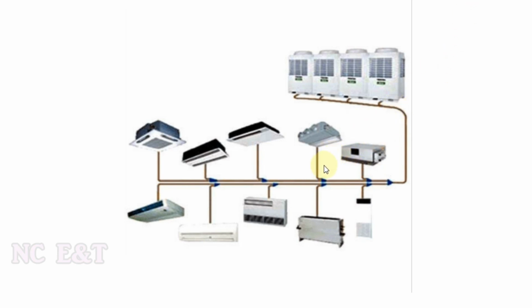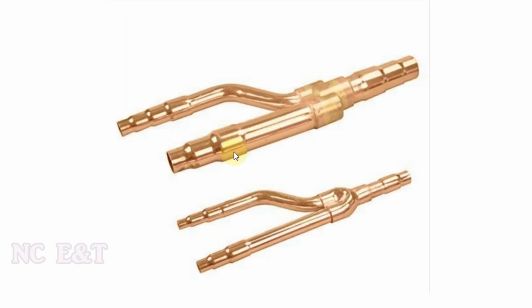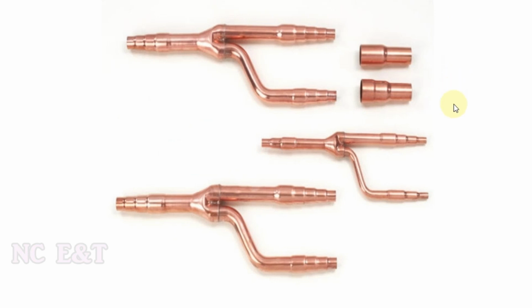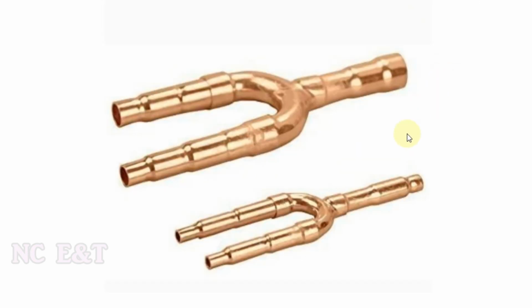When we connect the indoor and outdoor units to the piping network, there are some special fittings provided by the manufacturer of the VRF system. Each manufacturer of the VRF makes their own Y. They are nearly similar, but there is a little bit of difference. For example, we can see two or three of them. This is the Y manufactured by one manufacturer of the VRF. It is manufactured by another manufacturer, and this one by another manufacturer of the VRF.